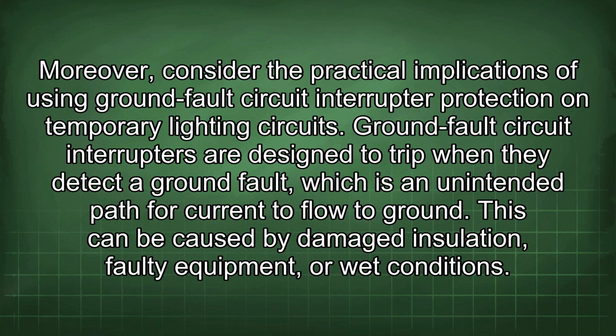Moreover, consider the practical implications of using ground fault circuit interrupter protection on temporary lighting circuits. Ground fault circuit interrupters are designed to trip when they detect a ground fault, which is an unintended path for current to flow to ground. This can be caused by damaged insulation, faulty equipment, or wet conditions.